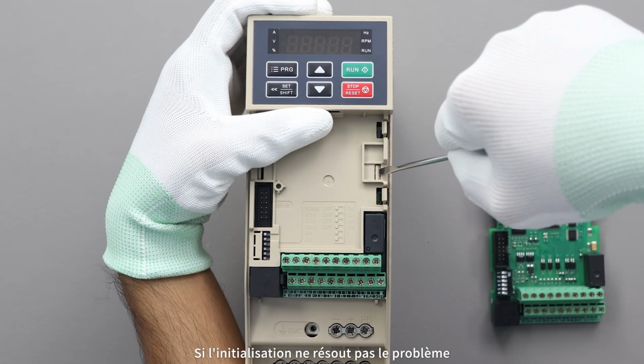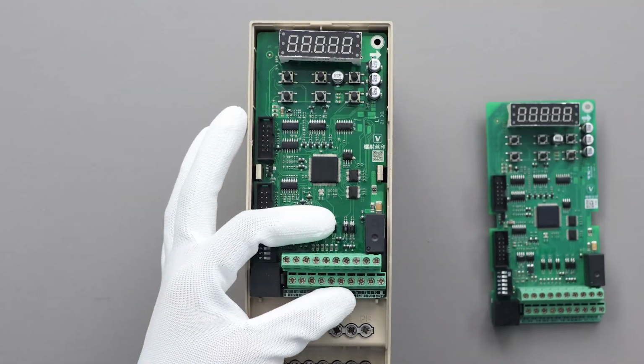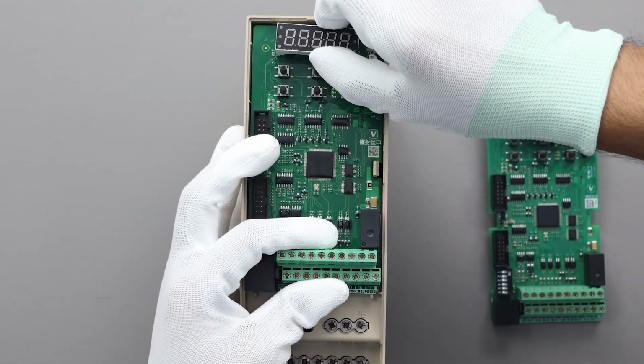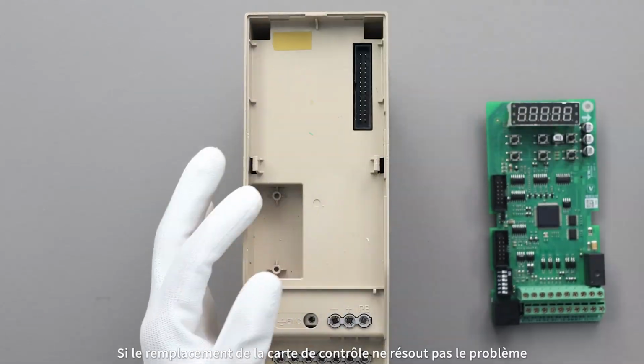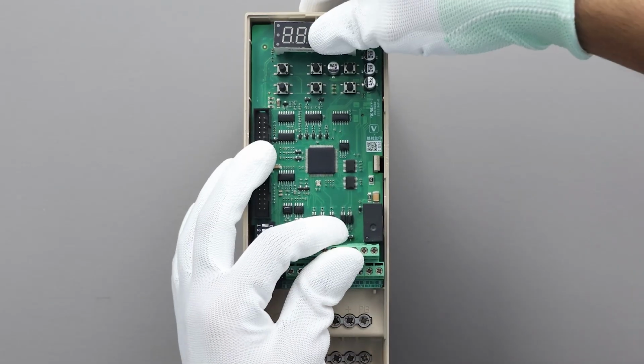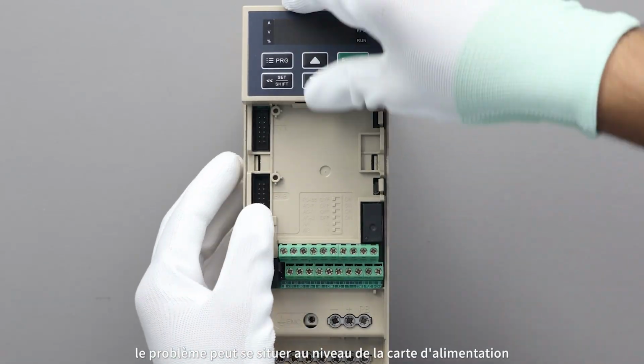Control board, power board. If initialization does not solve the issue, replace the control board. If replacing the control board does not resolve the fault, the issue may be with the power board.